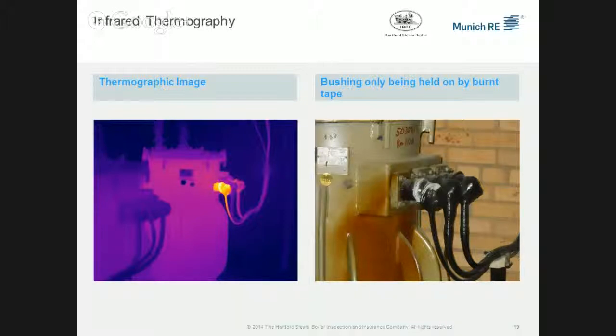But you went in there with an infrared camera, and you can see it shows bright as day. So we know we had a problem there. When we did the repair, it took less than 2 or 3 hours. All it was, was this connection. We replaced the connection with the bushing, and we're good to go.